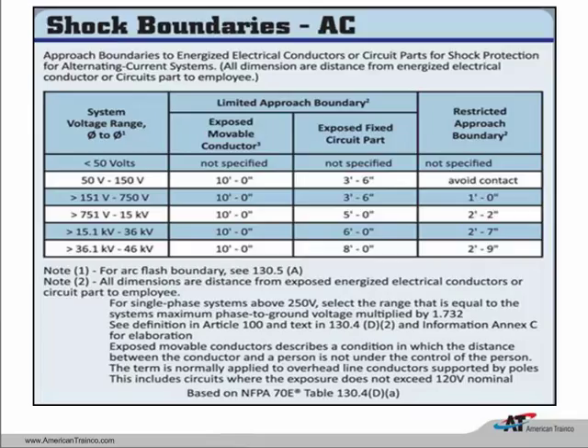There is no limited approach boundary, no restricted approach boundary. If we're below 50 volts and the equipment is safe, then we don't have to worry really about any type of shock protection there. The next boundary, though, 50 to 150 volts. In 2012, that range actually went from 50 to 300. So what they're doing for us here is they're giving us a chance to work on 120 volts a little bit with, in reality, no arc flash PPE required, especially on 120 volt control circuits.